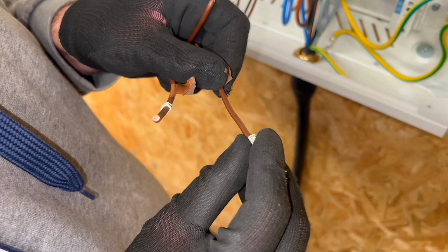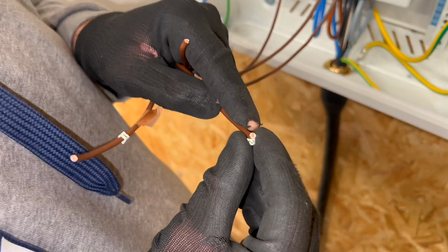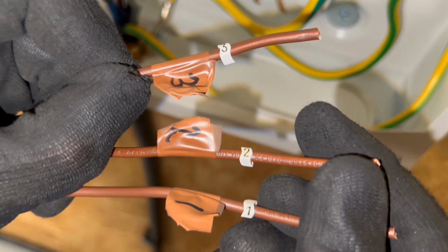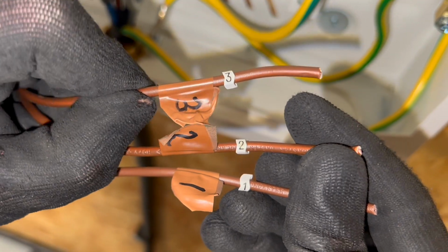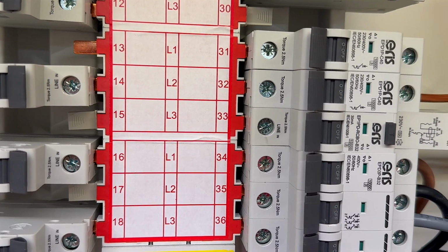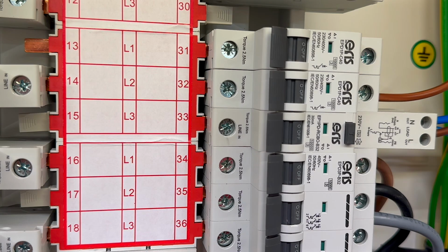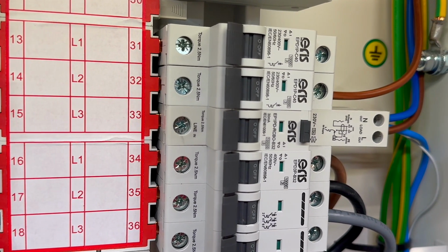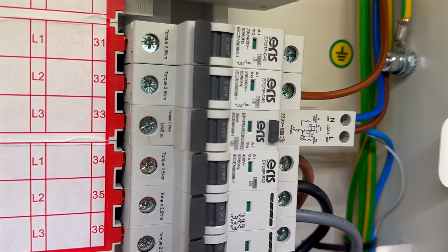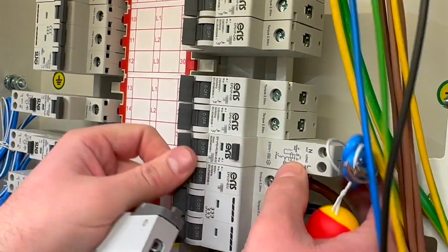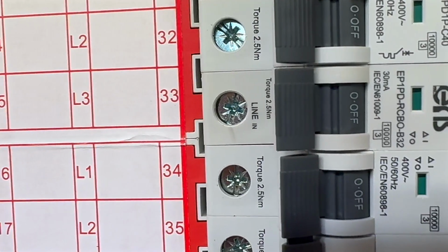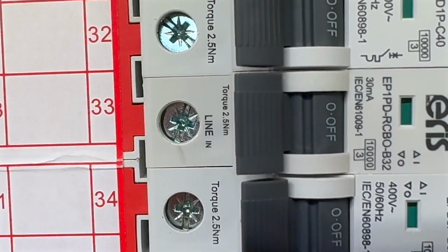It's also worth noting that a 3-phase circuit could be wired entirely with brown conductors, identified only at the terminations. Additionally, in a board supplying single-phase loads, such as a circuit supplied by L2, black phase, the outgoing circuit is likely wired using brown. Always double check to avoid confusion. Devices are easily fitted to the bus bar tabs. Along with all terminals, the manufacturer's torque settings should be followed. These can often be found printed on the device.